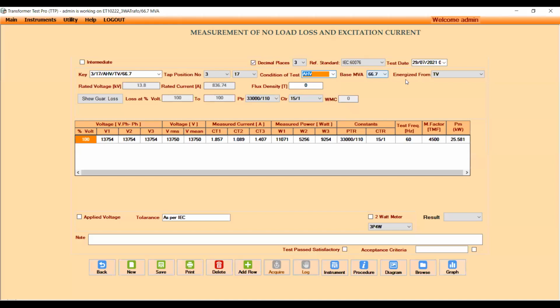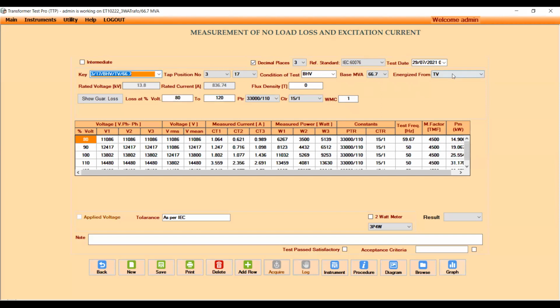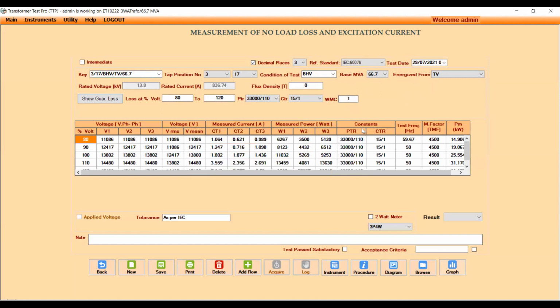You can also see the base MVA here. And when you conduct this no load loss test, you can choose where you are going to energize from. In this case, the tertiary winding. The moment you choose another key, you will also find that the no load loss test was conducted, again energized from the tertiary winding. So all these combinations you will be in a position to see. You can also see the guaranteed losses, as we have seen earlier, just for information.